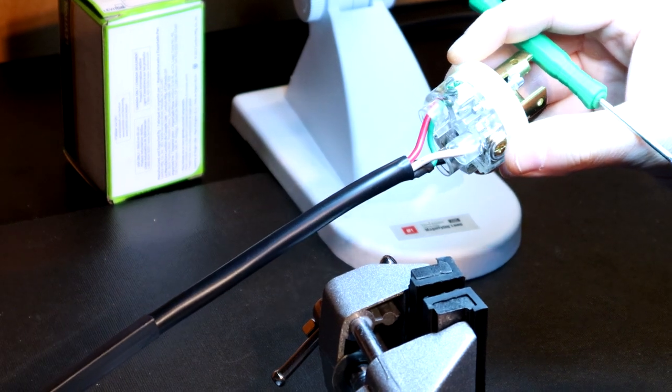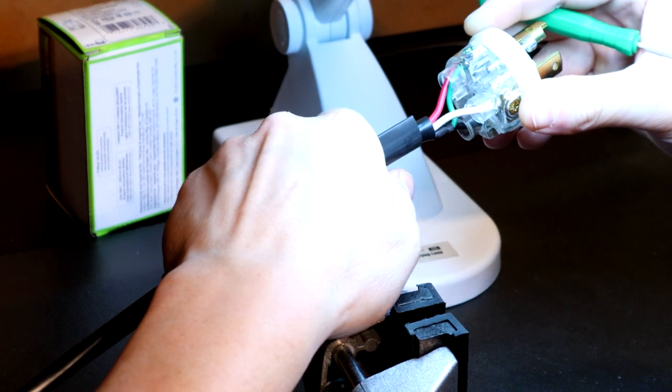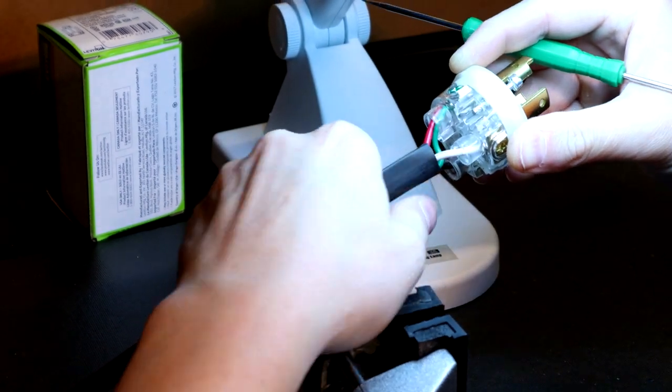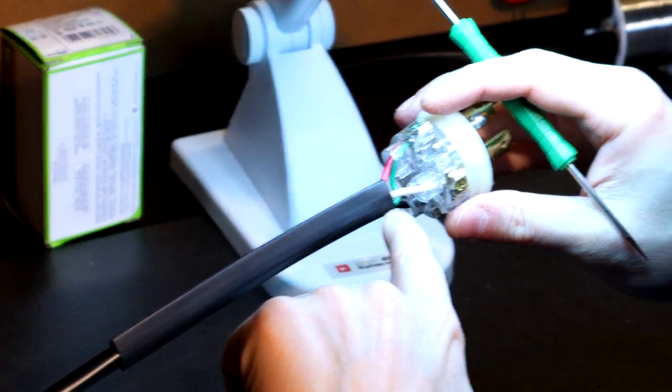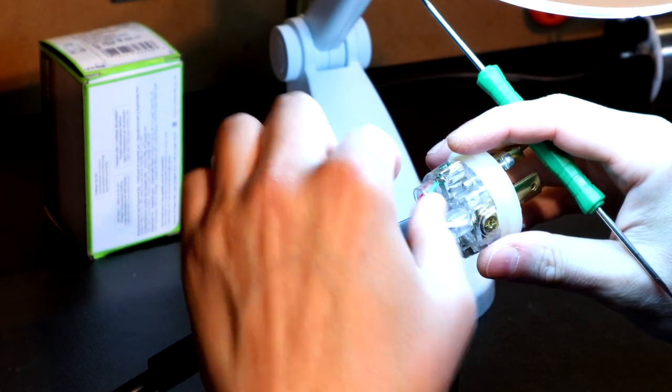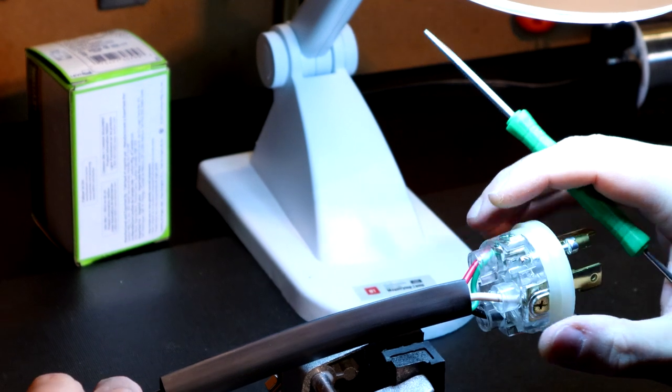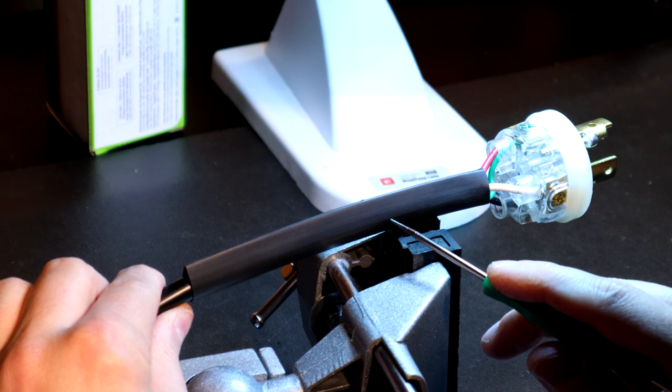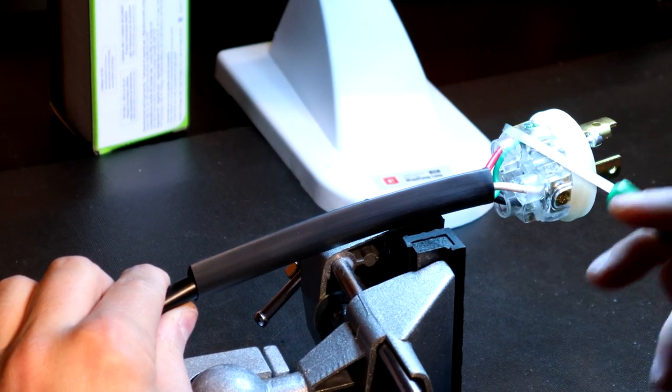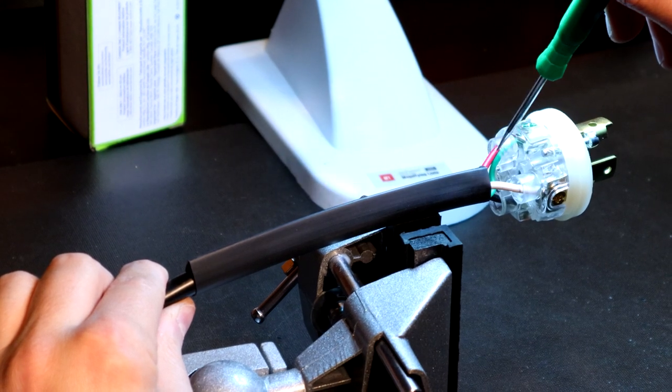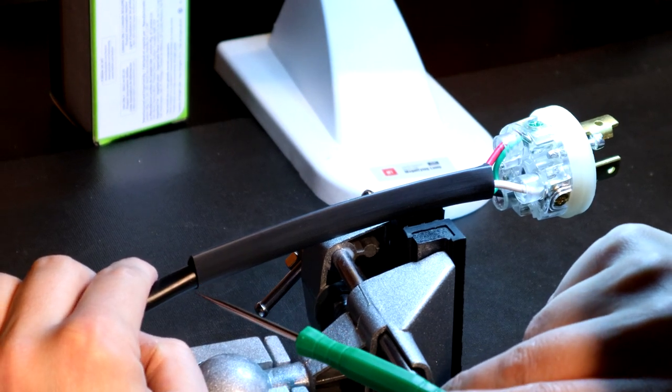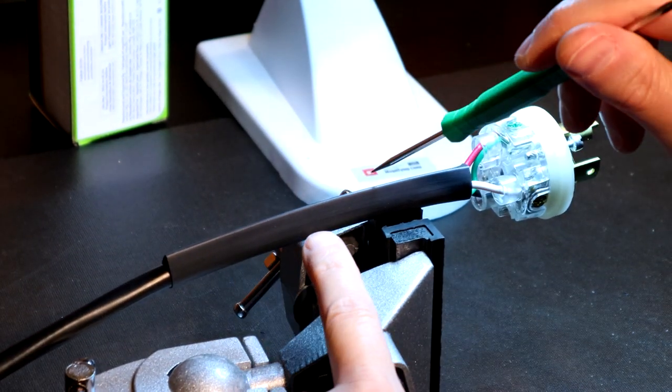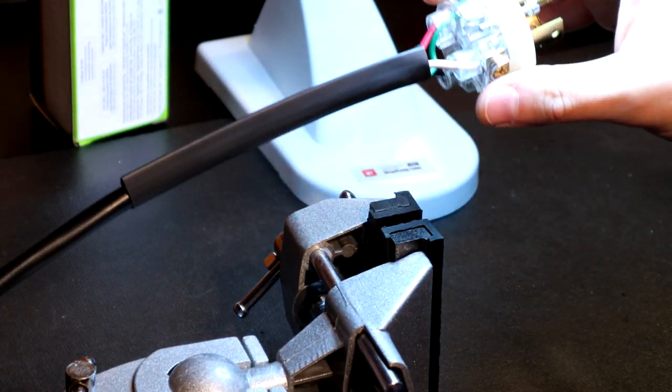The finishing of this cable is done very simple. I'm going to come up here with double wall heat shrink with adhesive. Why do we want adhesive? Adhesive is used to lock this heat shrink in place. I don't want to come all the way up here and cinch this all the way down. A lot of guys do that, and all you're doing is putting excess stress on your leads. What you want to do is stay beneath the wire where it actually ends and come back here and put the heat and make what's known as a boot.